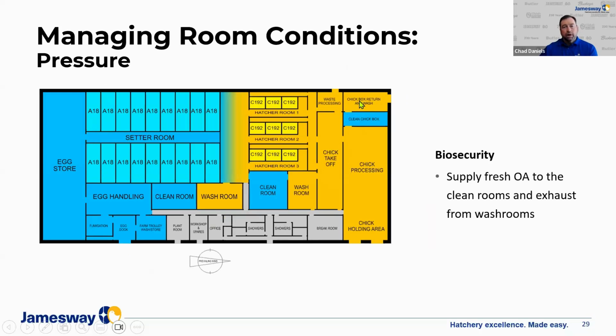So this is a very dirty area. And when they're cleaned, then they're stored here. So to ventilate these two spaces, similar with this clean room, washroom here for the baskets and for the trolleys, we supply fresh air into the clean rooms, and then it's pulled through the washroom, and then we exhaust that air out of the washroom.